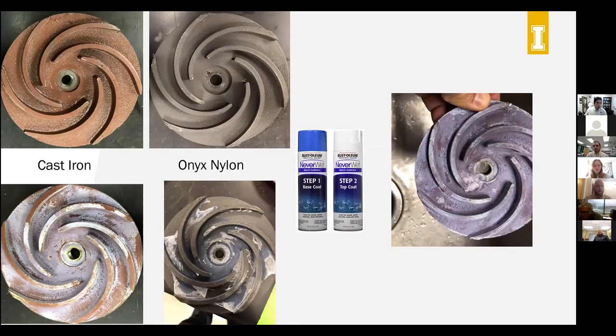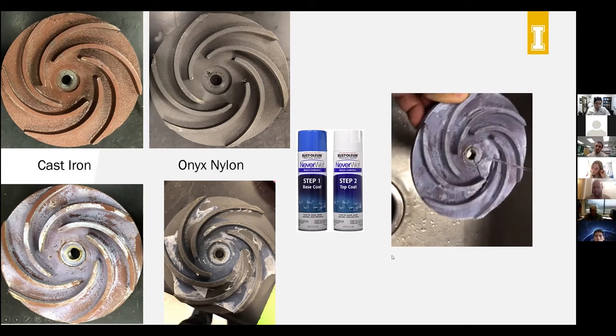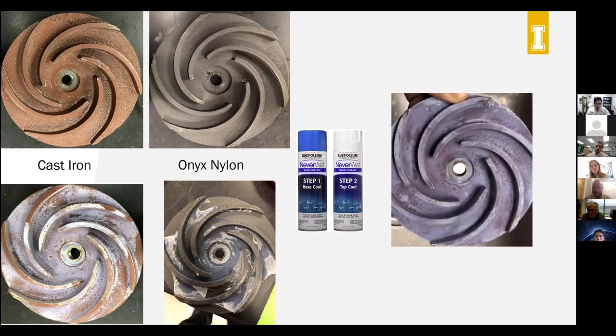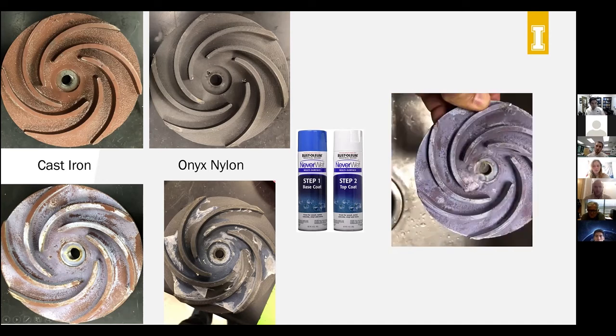And here you can see what the hydrophobic coating looked like on the impellers after it was tested. On the top of the slide, you can see both the stock cast iron impeller and the onyx nylon on the right side. And on the lower half, you can see how the hydrophobic coating sort of wore off after testing and underwent all the high pressure of pumping a high gallons per minute. And on the right side, you can really see how the hydrophobic coating rubbed off on the outer edge of the disc of the impeller. And to visualize what the hydrophobic coating does, there's a clip on the right. As you can see, it just kind of slides off the impeller a lot smoother than it normally would.